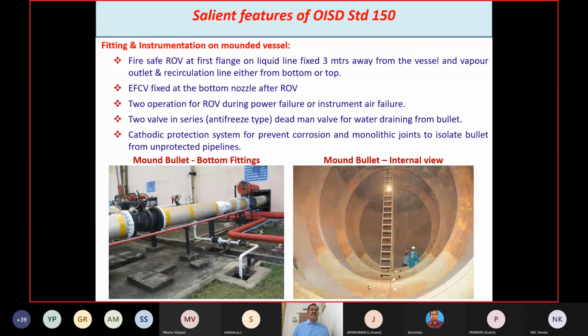One is for quick opening, and another of the throttle type, antifreeze type. And in between the two valves, one excess flow check valve also will be there. Mainly, while LPG is coming out, it requires heat, so it absorbs heat from the surroundings and also from the product and the pipeline. So if any water is mixed inside the pipeline, it will freeze and ice formation will be there, which will obstruct the valve, get trapped in the valve seat, and it will not close. So uncontrolled release of LPG will be there, and it will cause a very serious hazard. So this is a very critical operation as far as water draining is concerned.